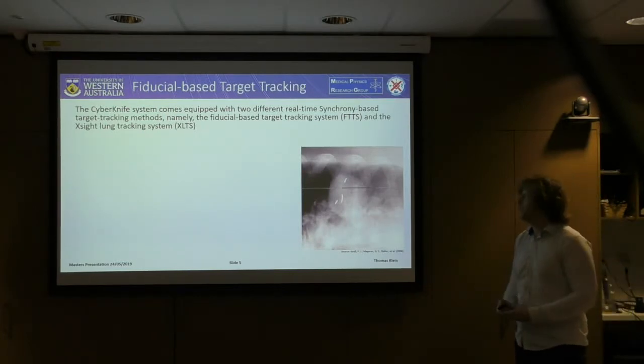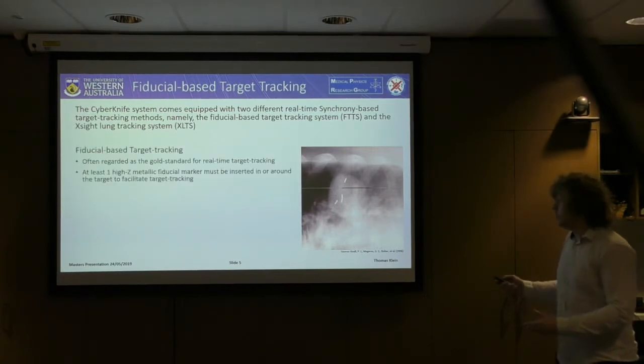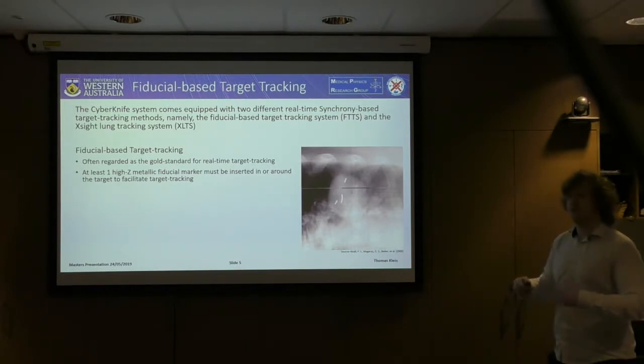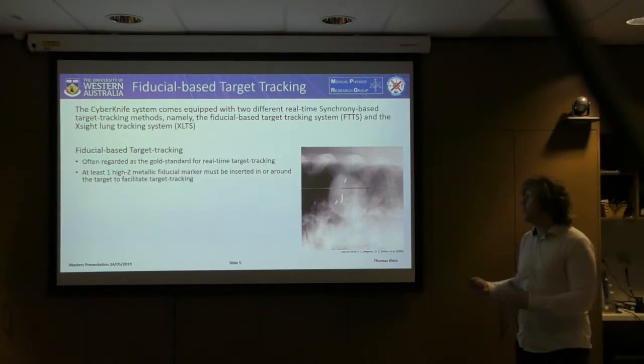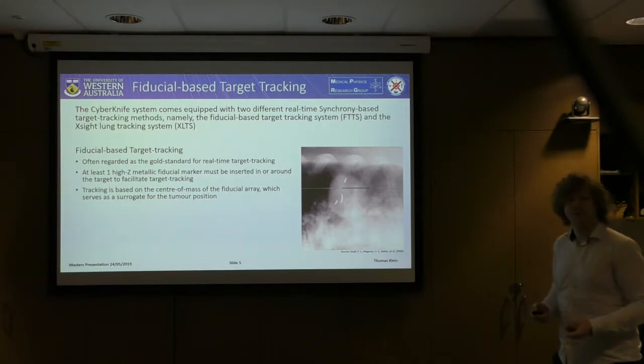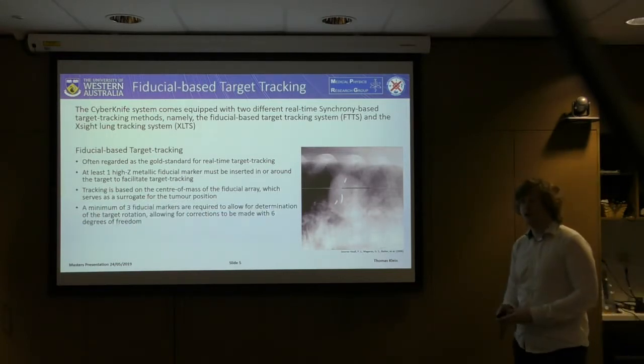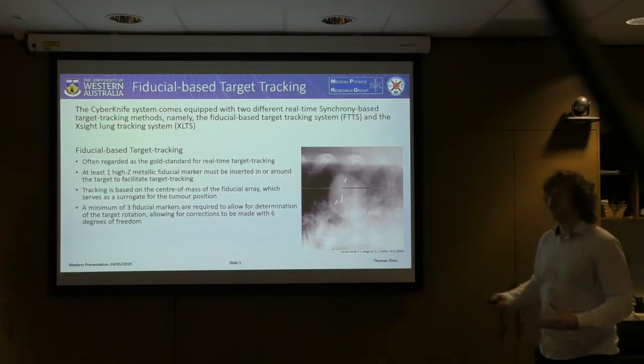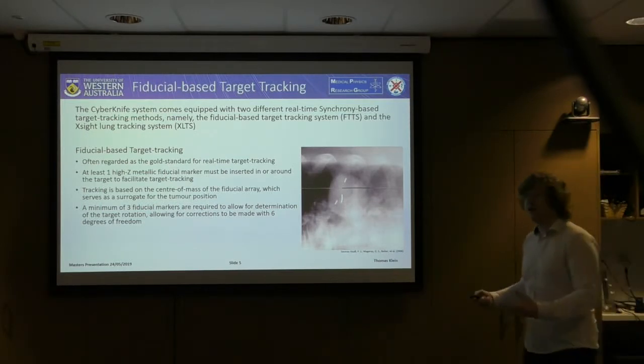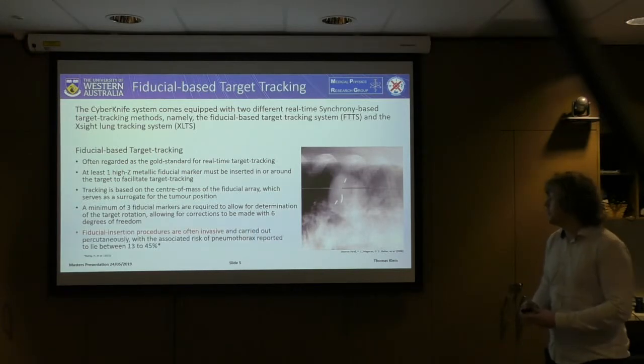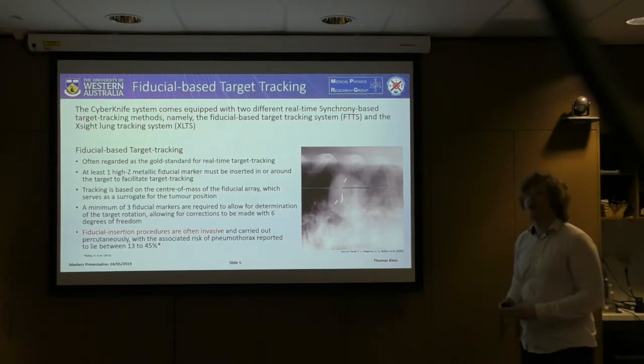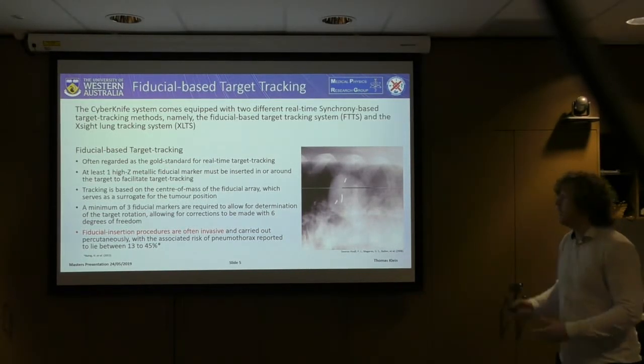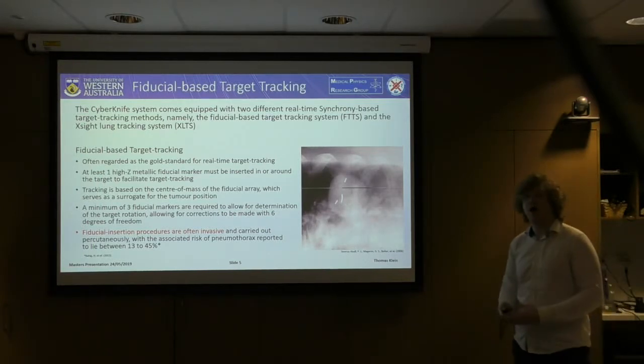The CyberKnife system has two different methods of real-time Synchrony-based target tracking. The first is the fiducial-based target tracking method, which requires at least one high-contrast metallic marker to be inserted in or around the target. Tracking is based on the centre of mass of the fiducial array. When only one fiducial marker is used, there isn't enough information to apply rotational corrections; a minimum of three fiducials are needed. Unfortunately, fiducial insertion procedures are invasive with high associated patient toxicities — pneumothorax rates have been reported as high as 45 percent.